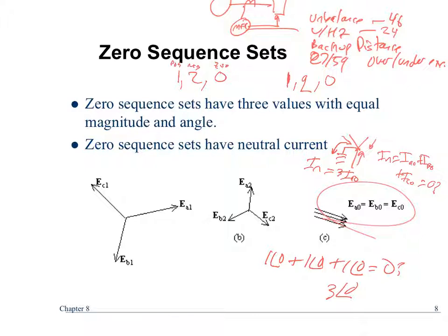So if you look at the relay manual, for their negative sequence values, sometimes they'll actually say 2, but if it says a Q in there, that's a negative sequence element, and it has to do with, if you remember back, we talked about how you transfer a set of non-rotating phasors to rotating. You use ODQ. This is direct and quadrature axis. If 0, 1, 2 is the normal sequence that we go, 0, then 1, then 2, why did they pick quadrature?